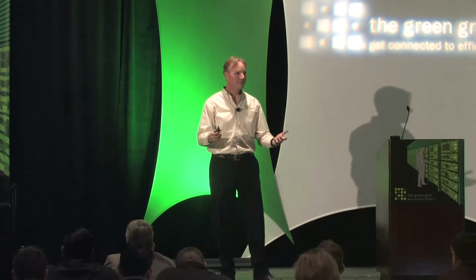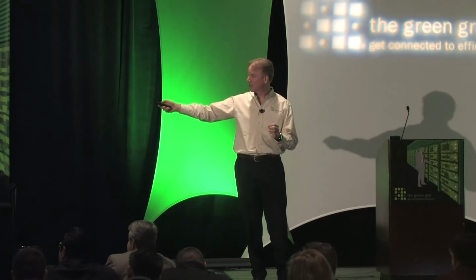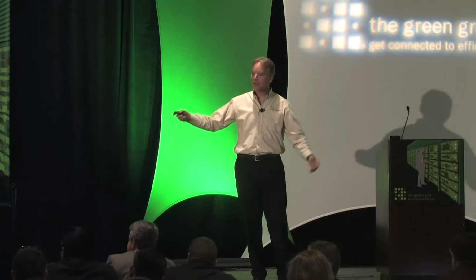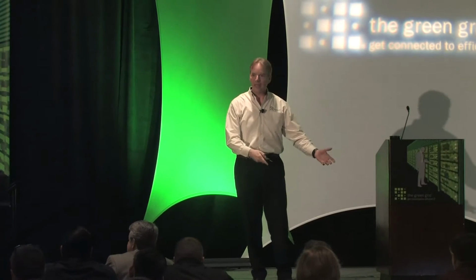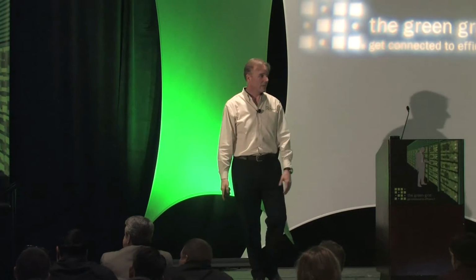What did that mean? Our overall site PUE, those numbers above, those numbers right here, went down because of containers, because those numbers are in here. So even if our white space is less efficient, the containers are making up for part of it while we're lightly loaded. And standard SKU is the reason. This is all the same kind of equipment, all rolled out inside of that infrastructure.